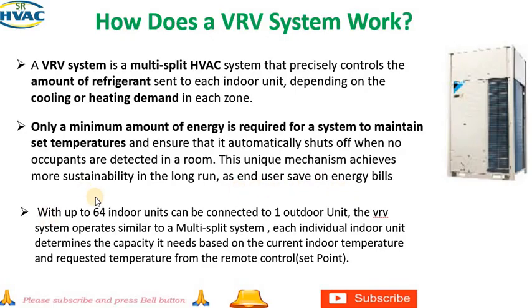Up to 64 indoor units can be connected to one outdoor unit system. The VRV system operates similar to the multi-split system. Each indoor unit determines the occupant's need based on the current indoor temperature and the requested temperature from the remote control. Either it can be set centrally or it can be set by the individual machines also.